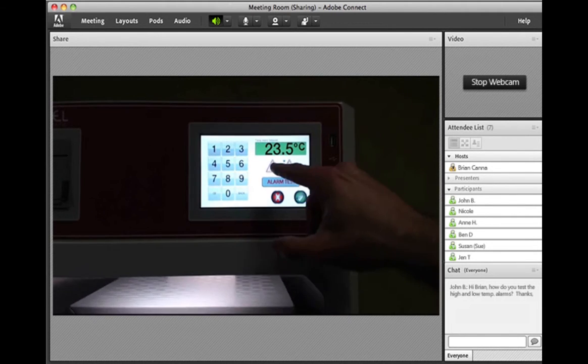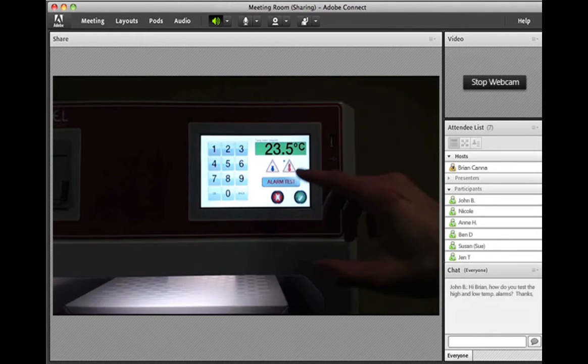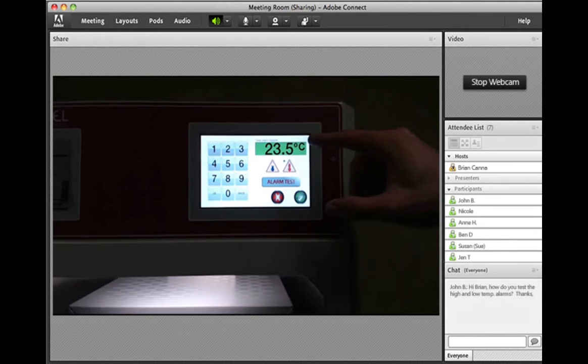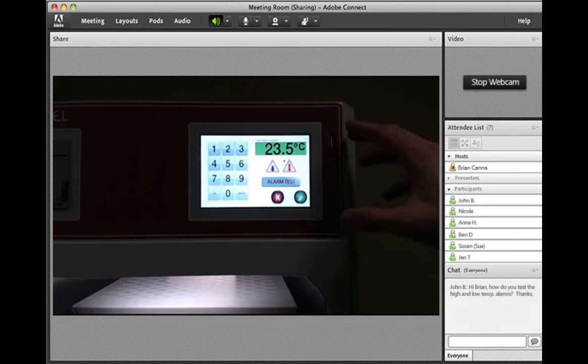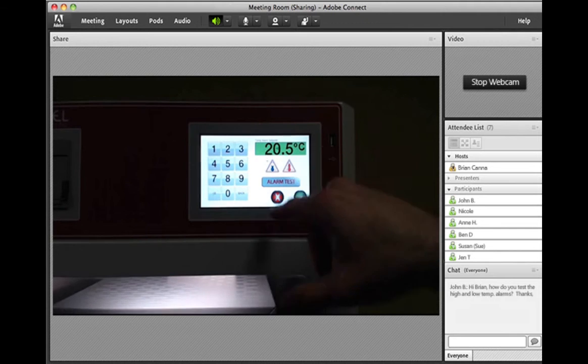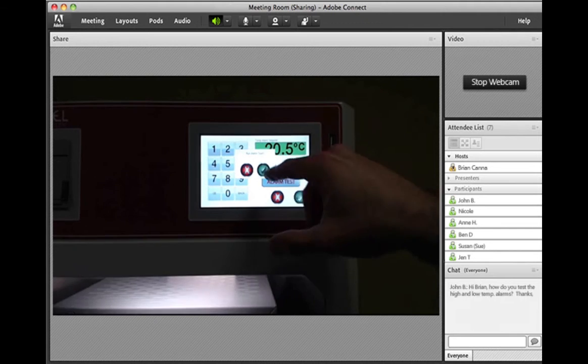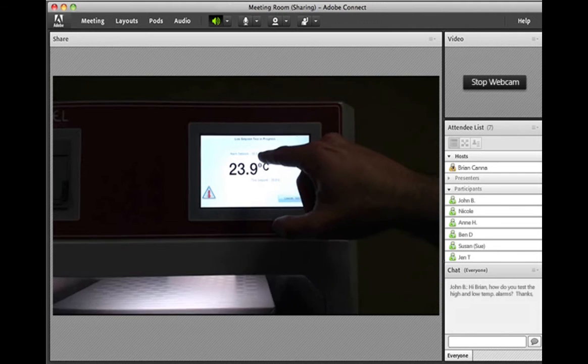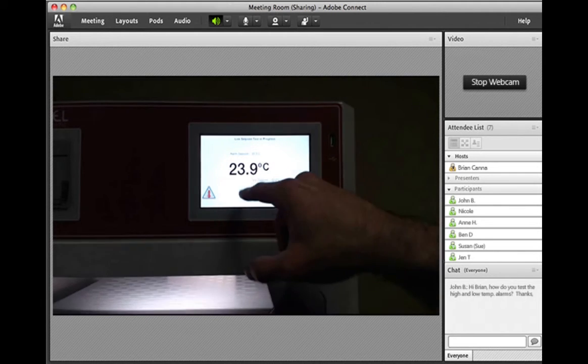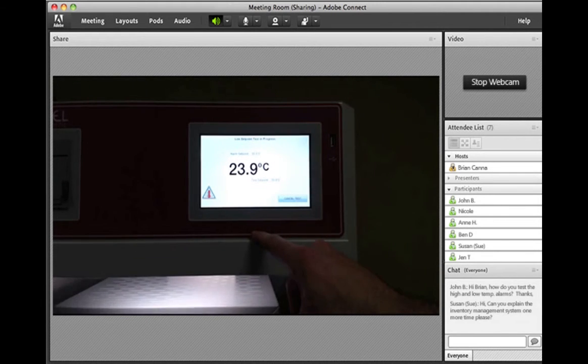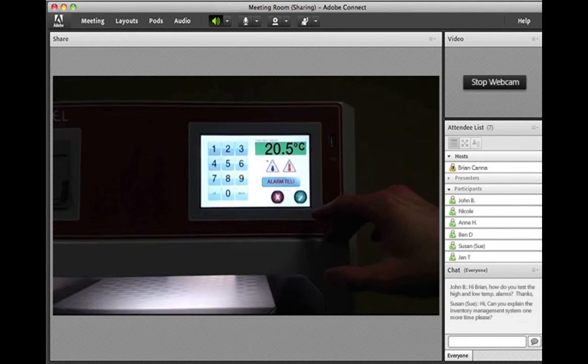And if we want, we can test the low temperature. It'll take a little time to do that because the temperature of the system is already pretty high. We'll just skip that, but what you would do is hit that and then go into here, and it will start bringing the temperature down to 20.5, and once that hits 20.5, it will alarm. But we've got a little while to go before it gets down there.